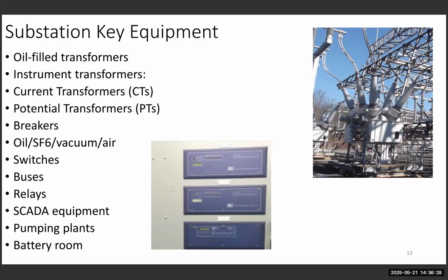Relays, you can see the picture here. I'm showing an SEL relay, the microprocessor one. Relays are the brain. If you don't have relays working properly, once you have failures, you can have very, very bad results. You could have extended outages, failures, fires. So part of the substation intelligence is to make sure that the relays are doing what they're supposed to do. Similarly, if SCADA is not working properly, then you don't really have any intelligence. And that's a big issue.